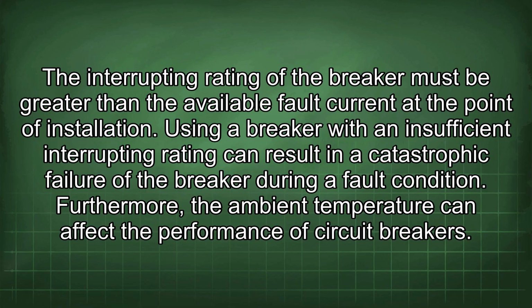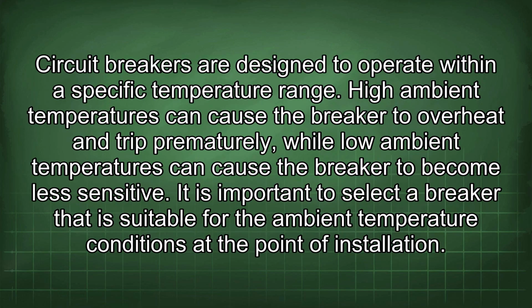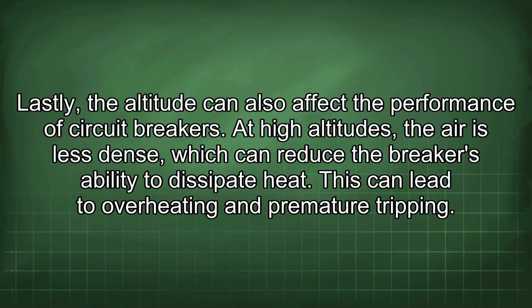Using a breaker with an insufficient interrupting rating can result in a catastrophic failure of the breaker during a fault condition. Furthermore, the ambient temperature can affect the performance of circuit breakers. Circuit breakers are designed to operate within a specific temperature range. High ambient temperatures can cause the breaker to overheat and trip prematurely, while low ambient temperatures can cause the breaker to become less sensitive. It is important to select a breaker that is suitable for the ambient temperature conditions at the point of installation. Lastly, the altitude can also affect the performance of circuit breakers.